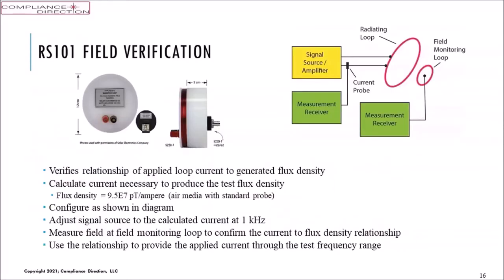RS101 field verification. This checks the relationship between the current flowing in the radiating loop and the field being measured by the monitoring loop. These things are built into each other, as we see on the left diagram. The monitoring loop and the radiating loop are standard equipment built with these parameters to the government spec. We calculate the current necessary to produce the flux density. Flux density in an air media is 9.5 E7 picotesla per ampere. So the idea is 950 nanotesla.